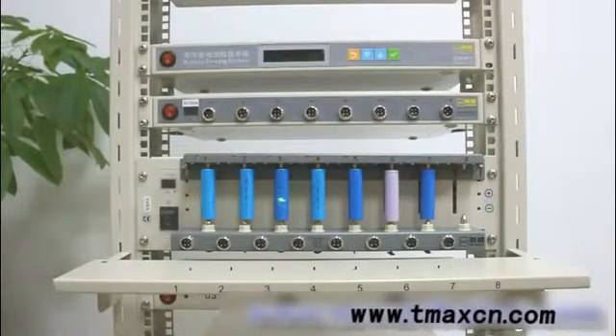Today we are using our BTS 4005 5V 6A and BTS 4005 5V 10mA as our sample units. We also have our mid machine here. For the mid machine, we recommend connecting a maximum of ten different testers, as that is the ideal configuration.